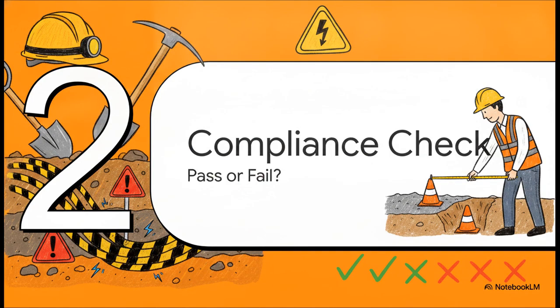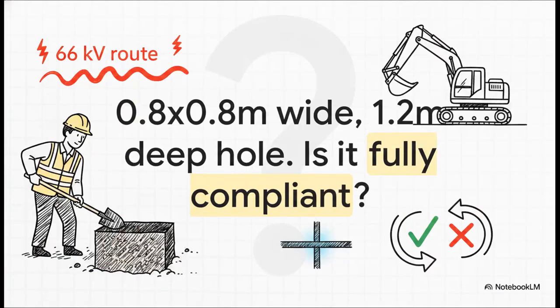Let's jump to Section 2, Compliance Check. Let's see if this passes or fails on a real site. Picture this scenario: a contractor is prepping a site near a marked 66 kilovolt route. They know they need to check the ground, so they grab their hand tools and dig a trial hole. They dig it 0.8 meters by 0.8 meters wide, and they go down 1.2 meters deep. The worker looks in, doesn't see a cable, and signals the excavator to roll in.